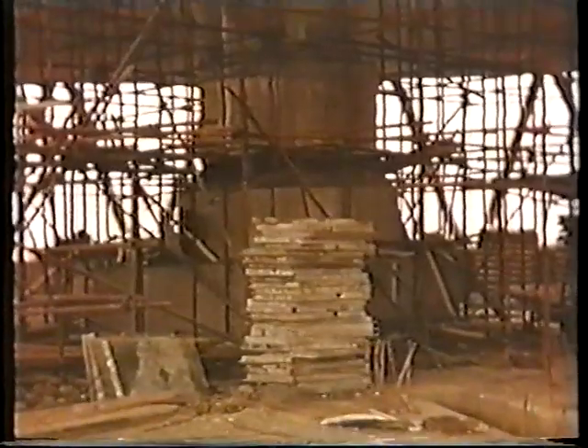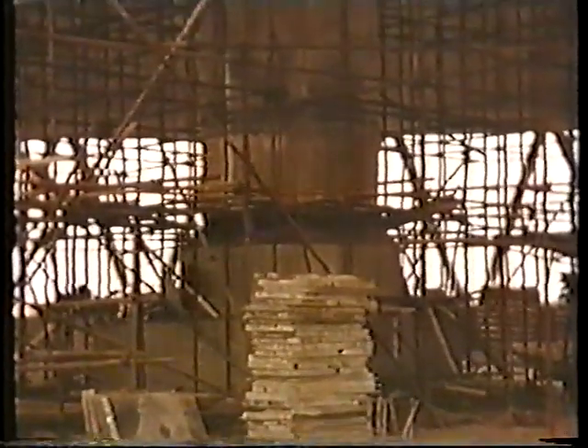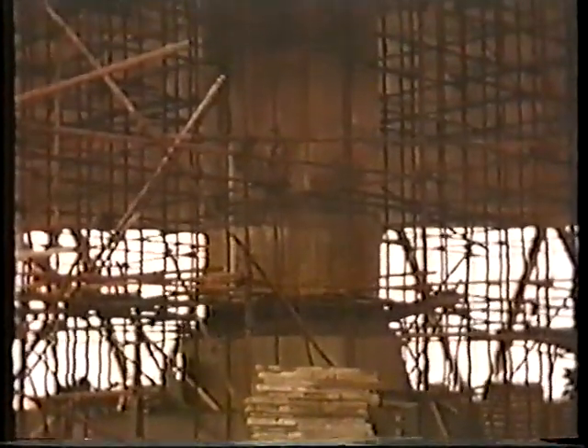In the base of the tower, treated wooden laths are fitted. Water is discharged from the center column to hundreds of jets and allowed to fall on these laths, which break up the water into tiny droplets. Air is drawn in between the tower legs, and the droplets are cooled as they fall into the pond below.